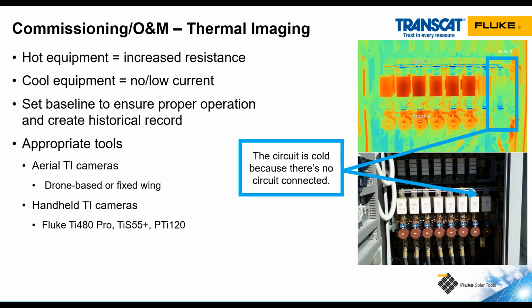the TI 480 Pro. As you go up in the camera range, the ability to take a high resolution photo increases. So the higher the resolution goes, the further you can be away from the component and still get good quality images. So if I have a high resolution camera, I can be outside the electrical hazard zone or arc flash zone of the equipment and still get a good thermal image. The TI 480 Pro also has interchangeable lenses, so I can add a telephoto or a wide angle lens to that camera as well.